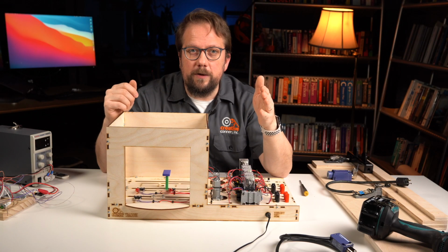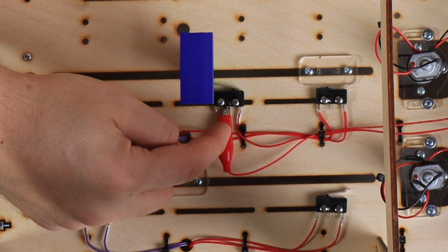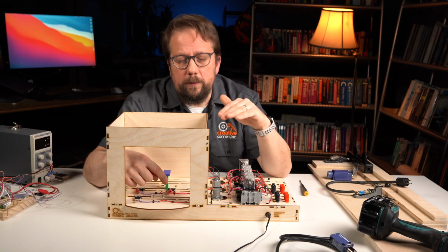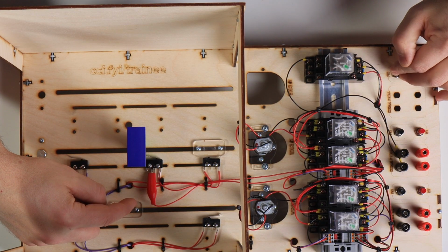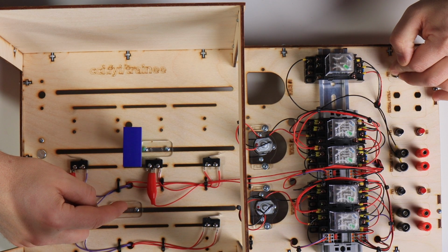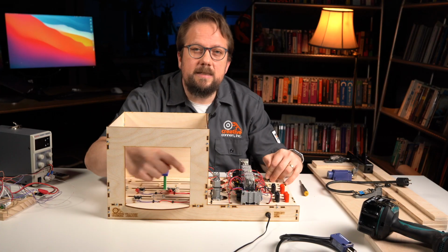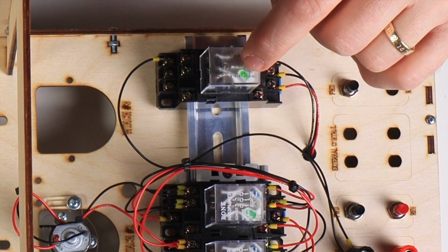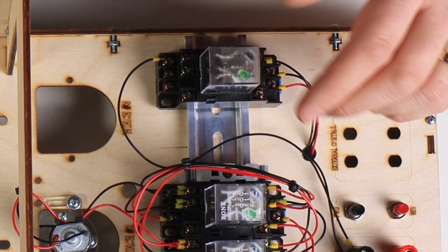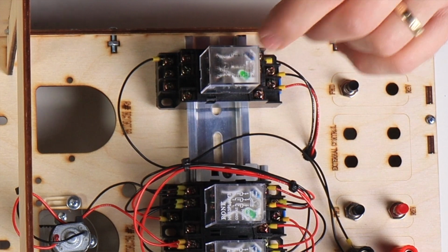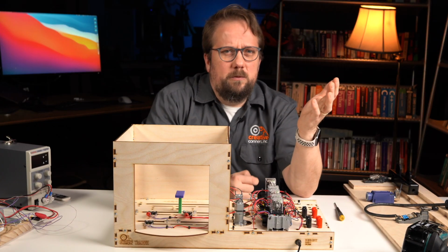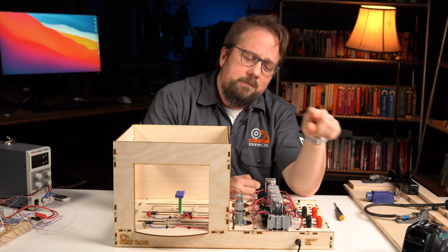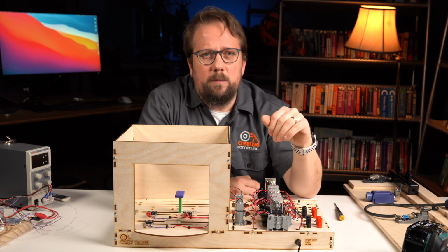I've modified my trainee and I've added another limit switch midway across the track. I've wired up this limit switch as normally open. That will stop the motor when it hits the switch. It sends a signal back to the control circuit indicating that it's been hit. You can see the LED light on the relay has illuminated, showing you that the limit has been struck. This sounds pretty reasonable, right? So keep quiet until you're hit. Then let me know and I'll go ahead and stop the motor for you.